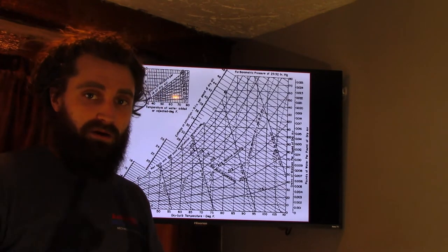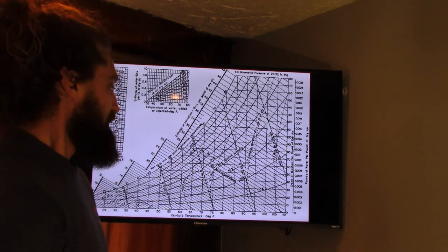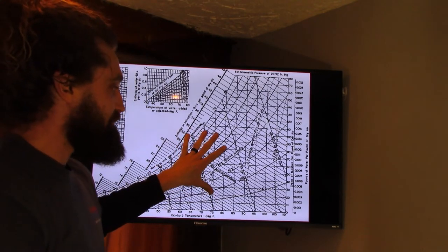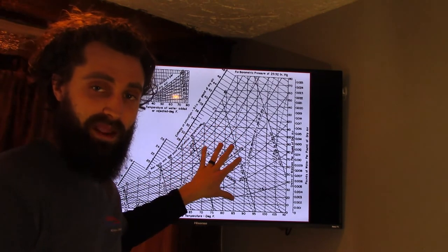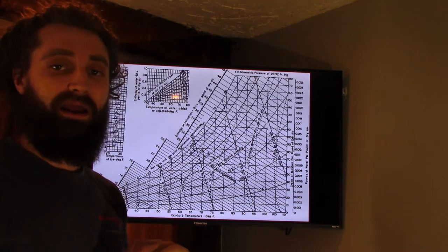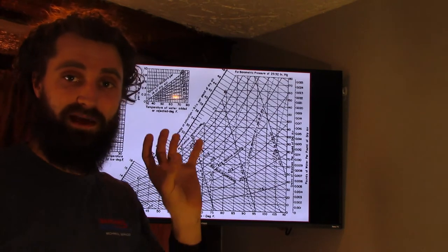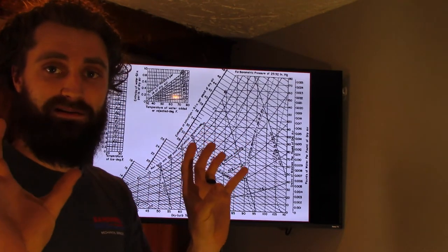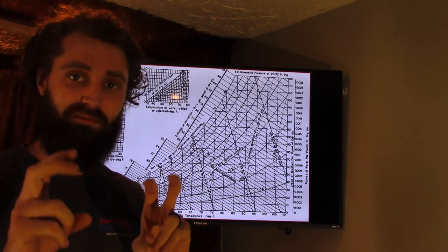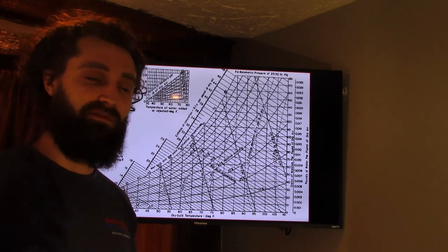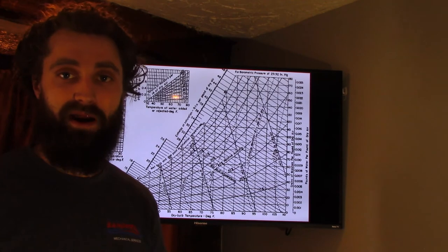So now, what I like to do is I'll actually take this a step further, okay? I will take this number that I get either from the hand calculation or from the app, and I will compare that to what the BTU capacity is of the unit. So we'll take that 34,000, divide it into that 36,000 of rated capacity, and I will get some sort of, I guess, thermal efficiency of that unit. But then from that, I can actually determine the SEER rating of a piece of equipment.